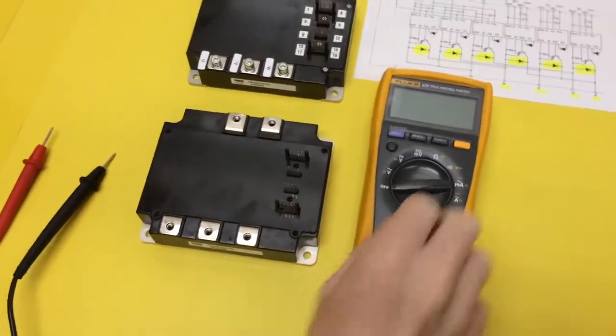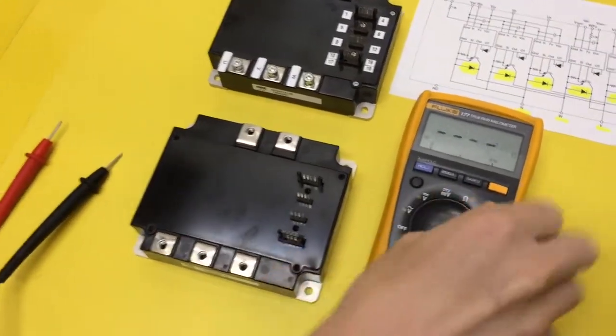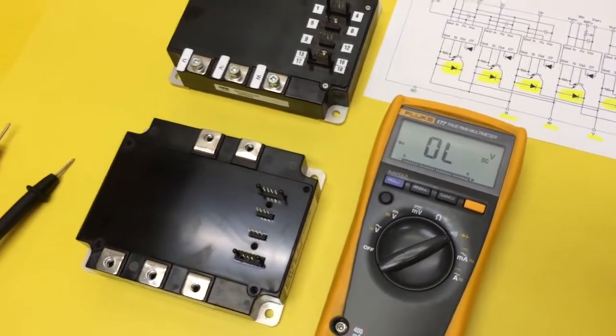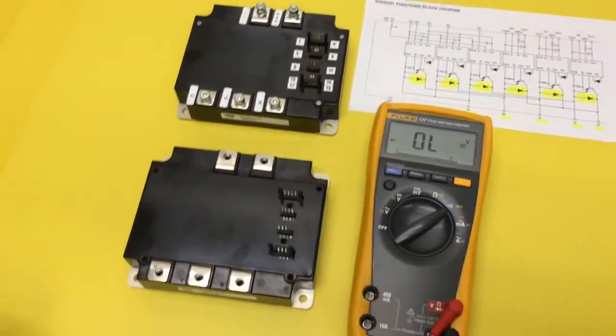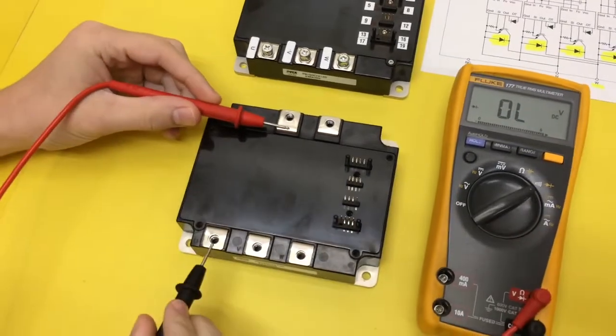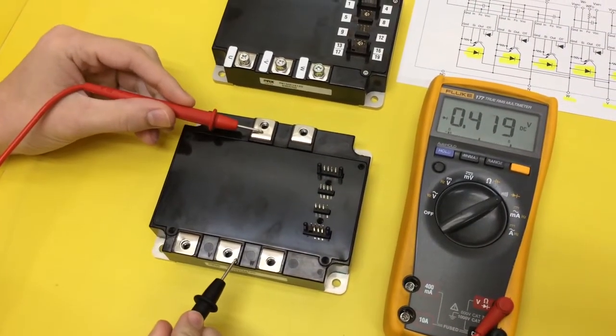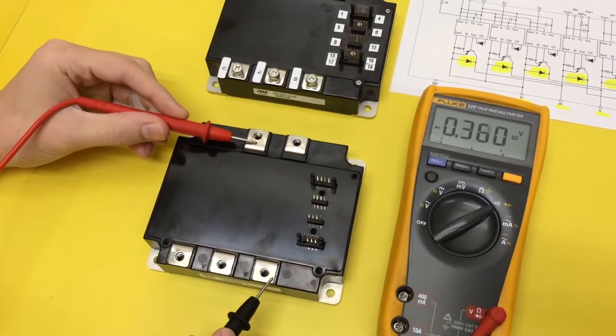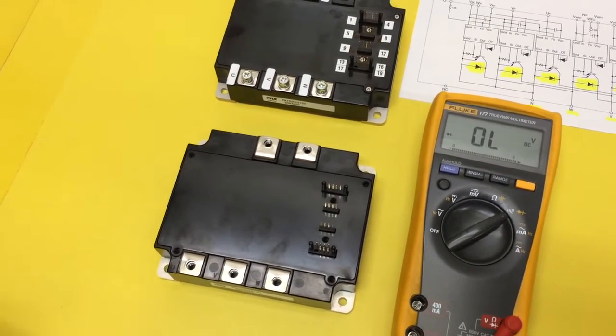Ryan, go ahead and put the meter on diode test scale. Alright, we're on diode test. He's just going to put his red lead on negative and then check all three phases. At this point, if one reads different, it's the culprit. Those all read good.